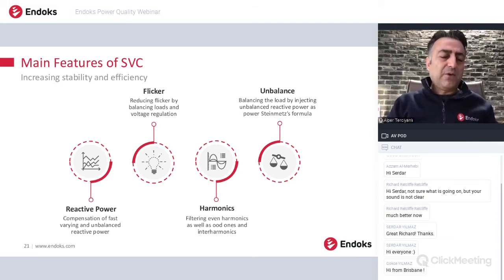But of course nowadays we are using new types of lighting in our houses, the most efficient ones. So these don't create flicker anymore, and the SVC can eliminate harmonics and it can eliminate the unbalance issues.